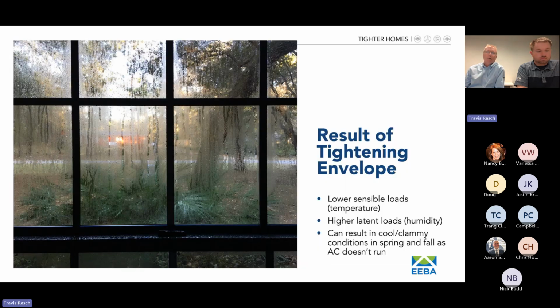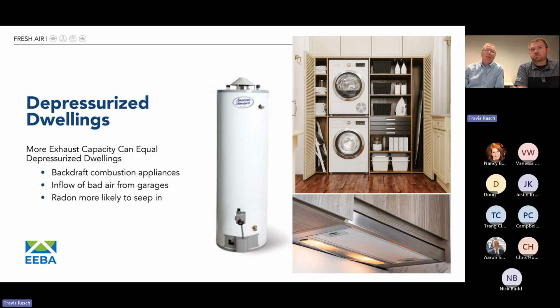So what happens? We tighten the envelope. Obviously, a good thing. We're going to lower the sensible loads. Going to make our home less expensive to heat and cool, but we're also going to increase the latent loads. All that shower and cooking humidity has no place to go now, so we have to think about that. So that can result in the shoulder seasons when it's not warm enough yet for the AC to run. Of course, your AC does two things for you. It cools, but it also dehumidifies. So if it's not having to run to cool, it's also not dehumidifying. So you can get very uncomfortable conditions in certain times of year.